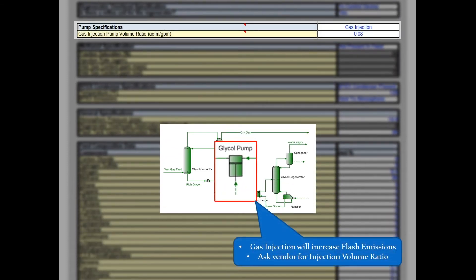Select whether the glycol pump in service is a gas injection pump or an electric pump. Kimray pumps are a common example of a gas injection pump — they require a low rate of high pressure feed gas to mix with the rich glycol, providing the motive force needed to increase the lean glycol pressure up to contactor pressures. For gas injection pump types, input the gas injection pump volume ratio, which is the ratio of high pressure gas used divided by the volumetric flow rate of glycol circulated — this should be provided by the pump vendor. Gas injection pumps lead to higher emissions, while electric pumps lead to no additional emissions.